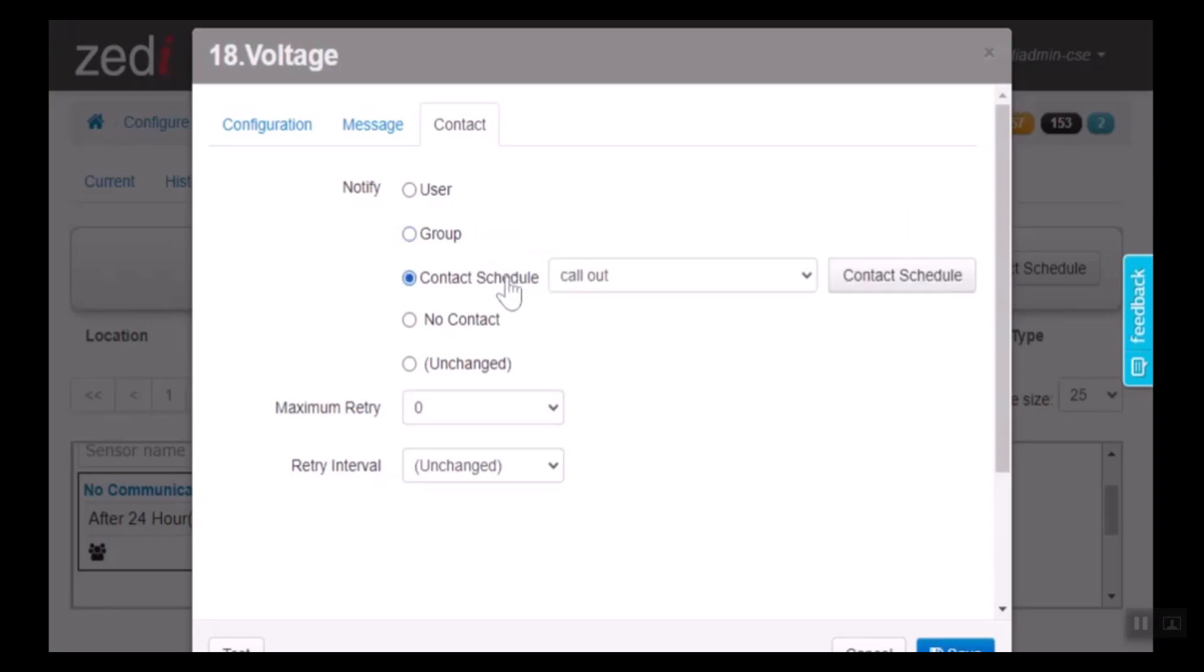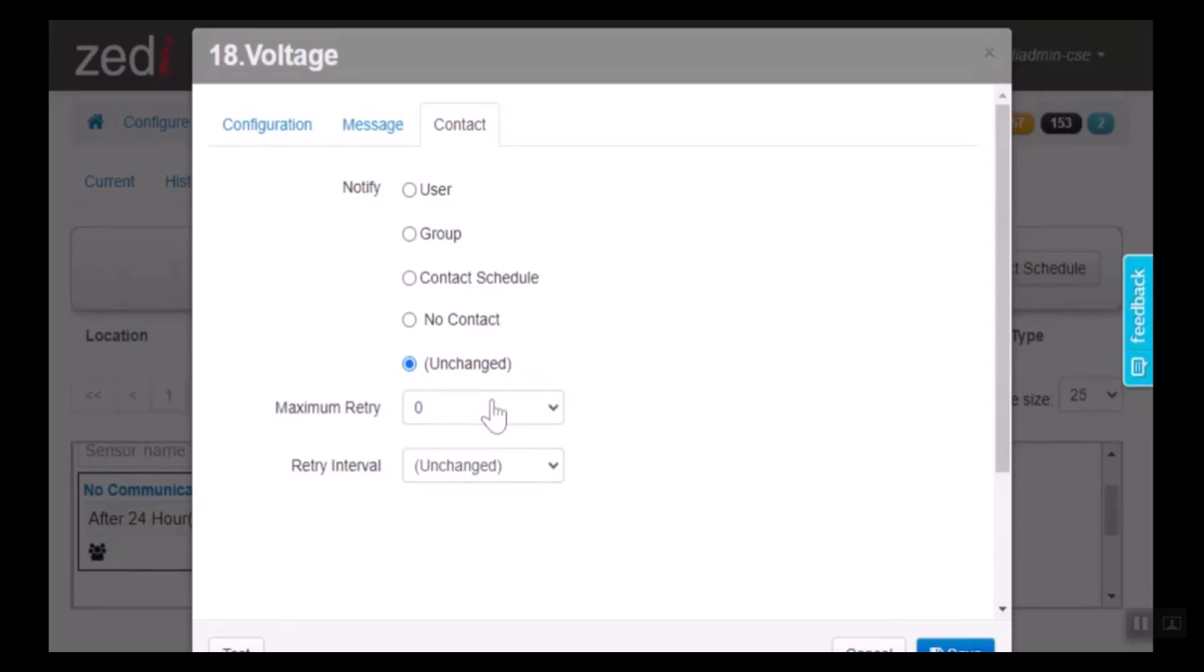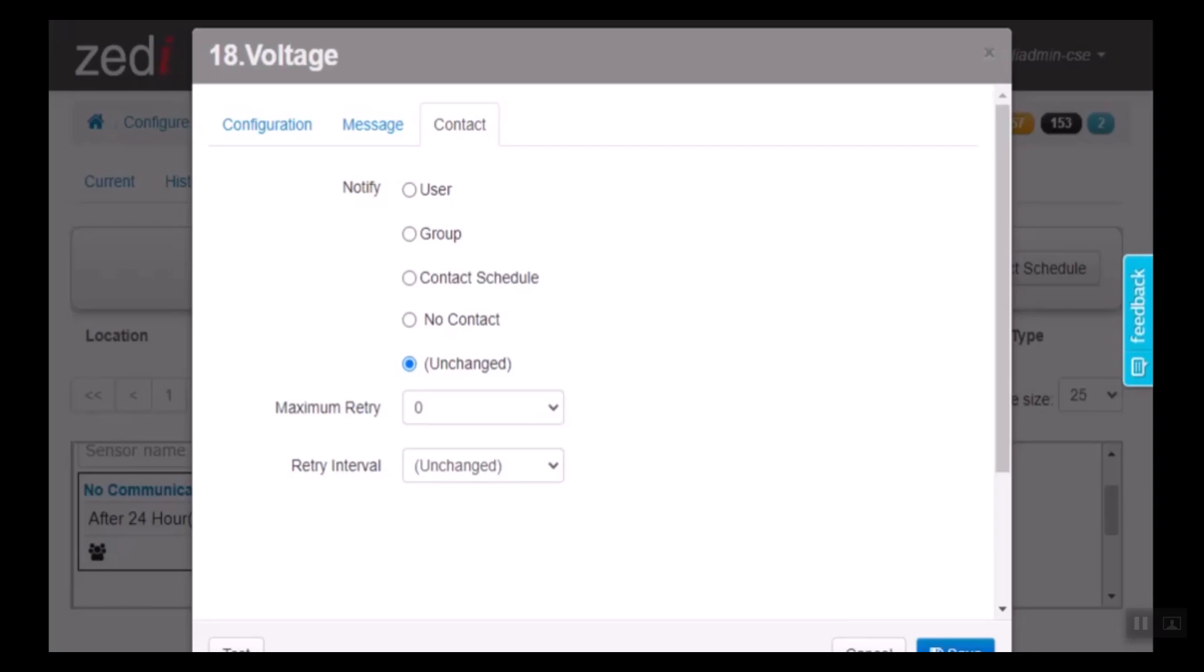We can create a contact schedule to identify each user at a specific time. We can have no contact at all, or we can create unchanged. Here we can have the maximum number of retries, so between zero and five retries and retry interval. Depending on how important this site is, you could have between 60 seconds to retry or between 24 hours.